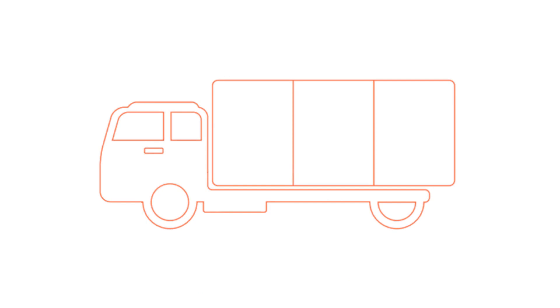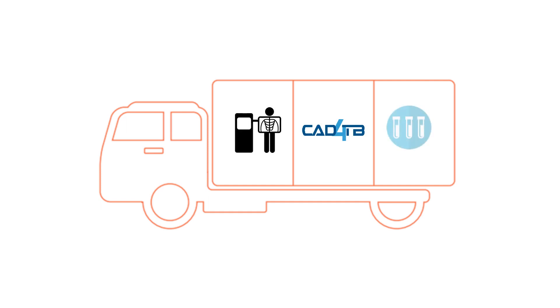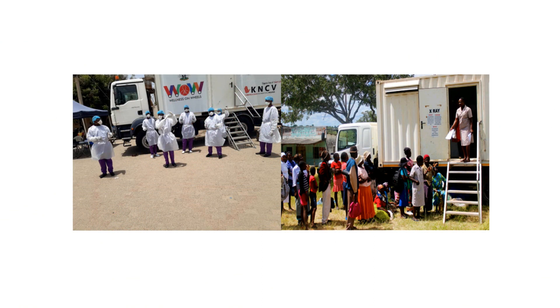Because this technology is targeted at people who have no access to hospitals or other healthcare facilities that can adequately screen for tuberculosis, there is a need to make the technology mobile — if the community can't go to the clinic, let the clinic come to the community. The CAD for TB service is made mobile by a truck with three important compartments: the X-ray section, where a mobile digital X-ray machine acquires chest X-rays; the section where the acquired chest X-ray is analyzed by the CAD for TB software; and the laboratory section, equipped with GeneXpert equipment for further testing. This truck is called the Wellness on Wheels truck, or WOW truck for short, and through an array of staff including radiographers, tuberculosis detection is brought to communities that really need it.